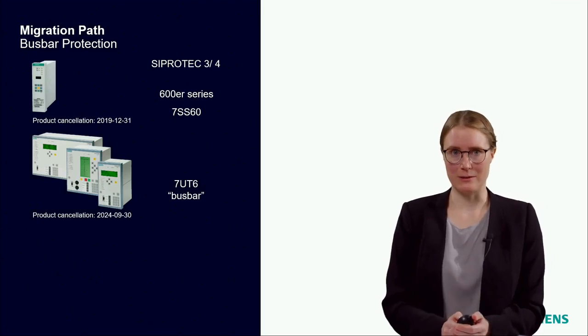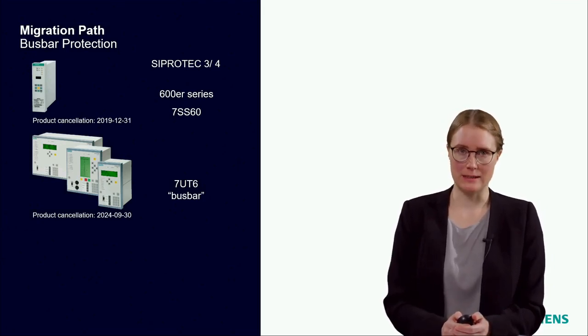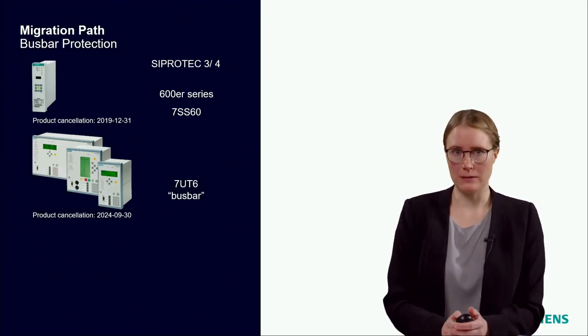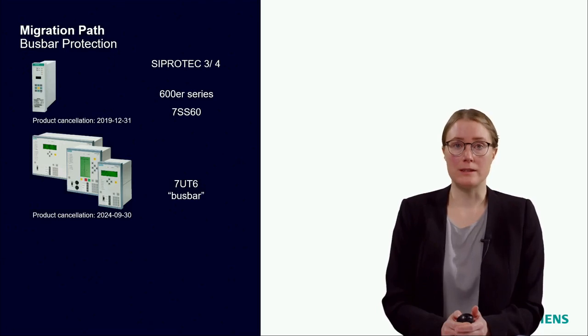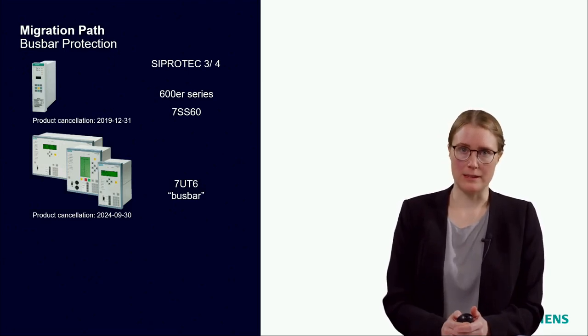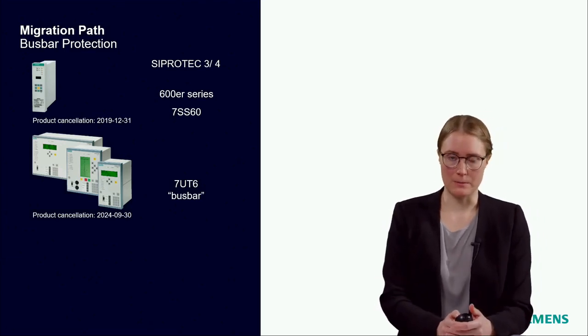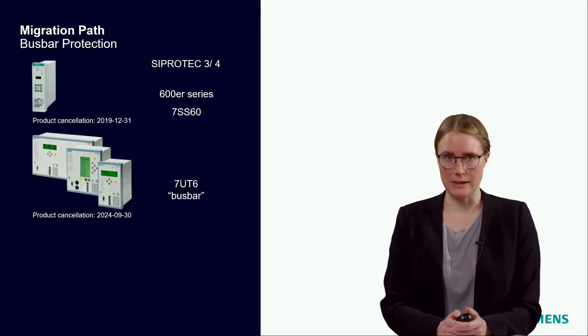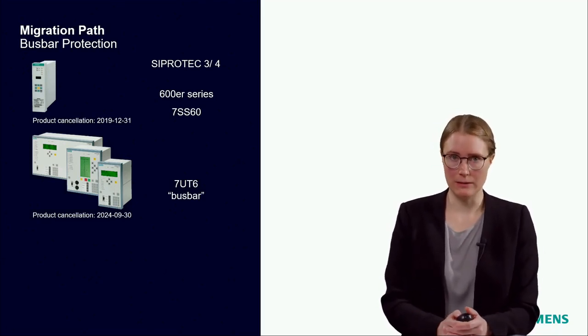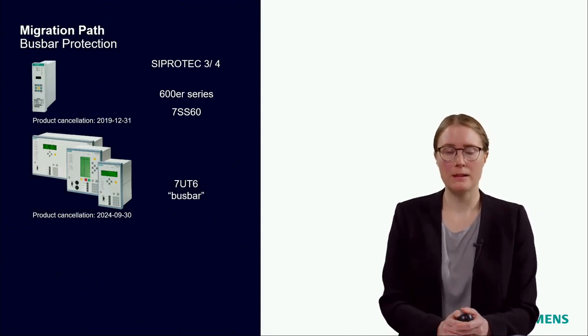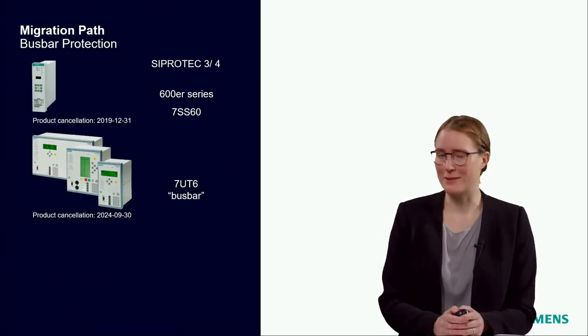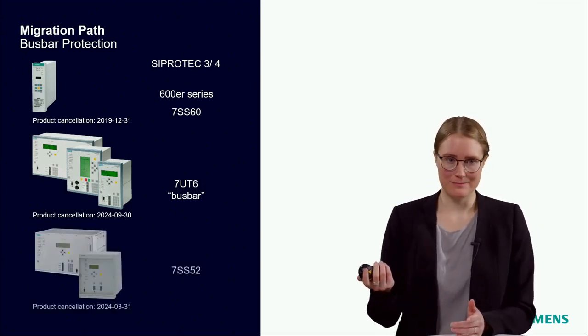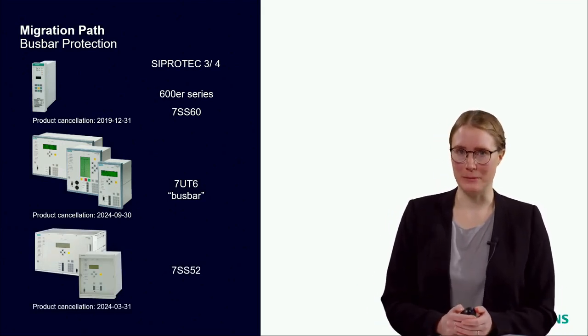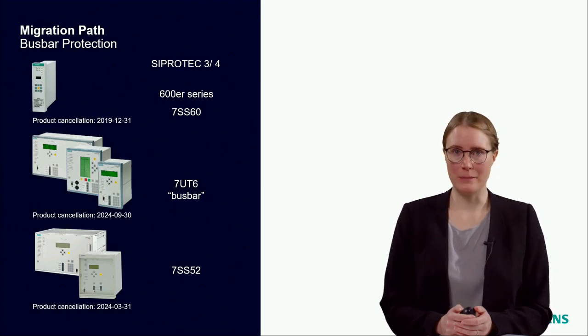The SIPROTEC 4 solution for centralized busbar protection is the 7UT6. The 7UT6 is actually a transformer differential protection device, which can be used as well for busbar differential protection. This was necessary because before the SIPROTEC 5 7SS85, we had no other SIPROTEC 4 centralized busbar protection solution. The 7UT6 can be used for single busbars with up to 12 feeders without sectionalizer. The 7UT6 devices are the ones in the middle of the slide. And of course, we have the 7SS52 in the SIPROTEC 4 portfolio. The 7SS52 is for complex multi-busbar systems in a distributed setup.